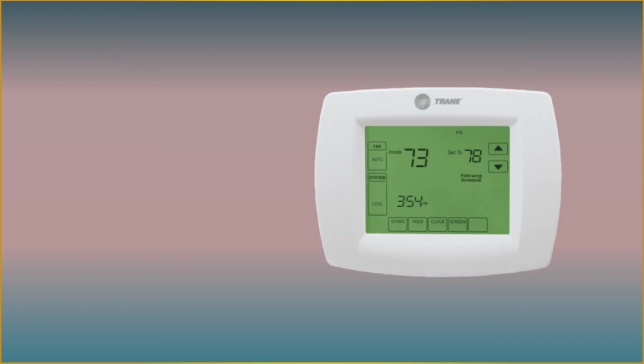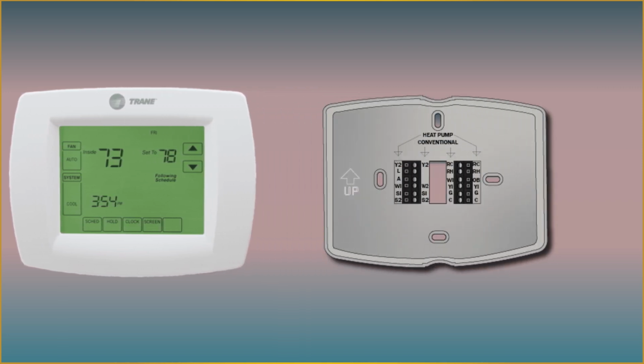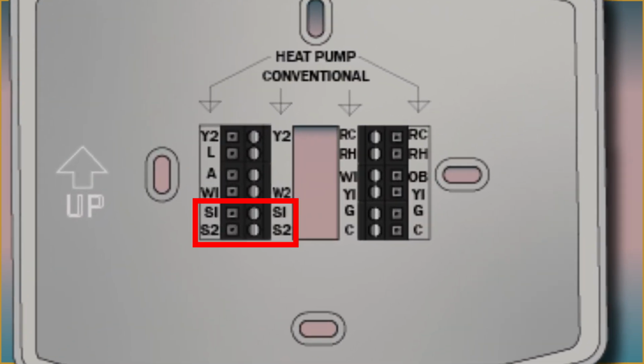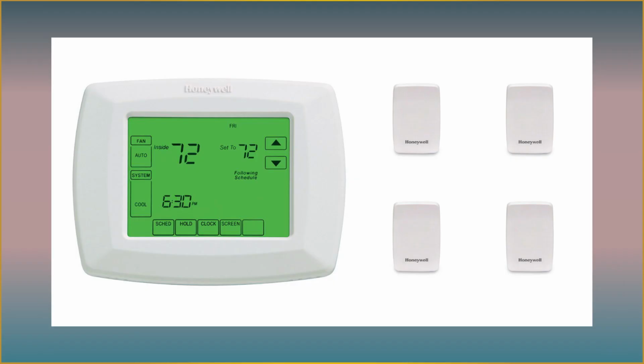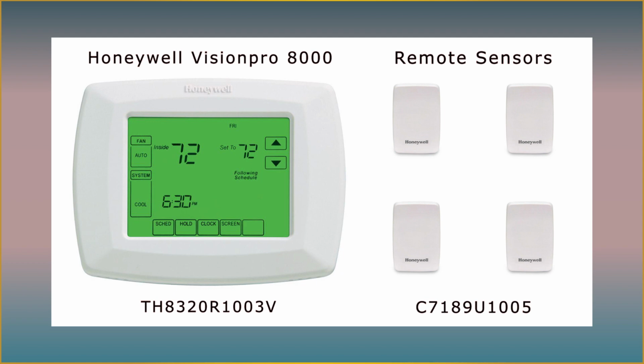First, check to see if the currently installed thermostat has the ability to have a remote temperature sensor added to it. Pop the thermostat off the subbase and look at the terminal strips. See if you see an S1 or S2 or T1 and T2. If it does, go to your supply house and pick up 4 remote temperature sensors for that model. If not, you might have to purchase a new thermostat like a Honeywell Vision Pro or something comparable.